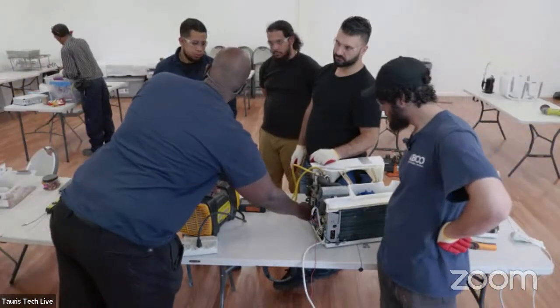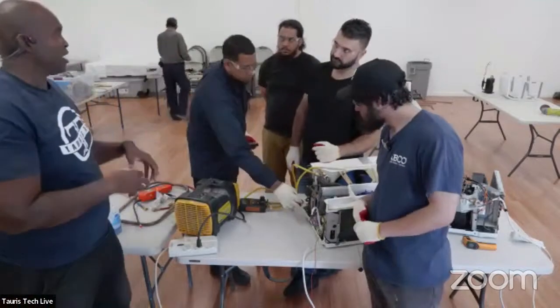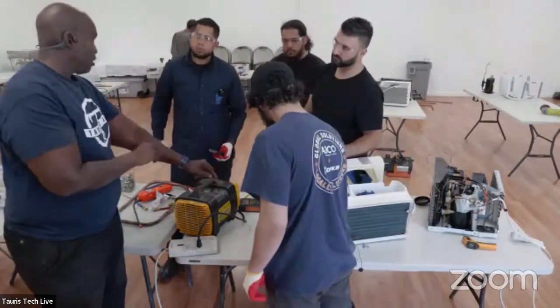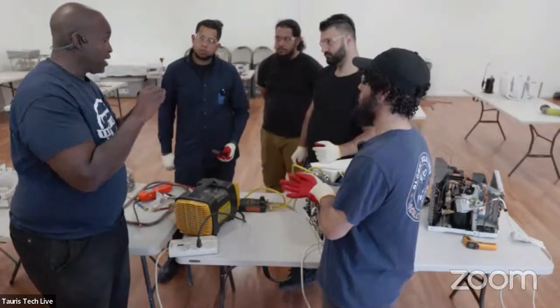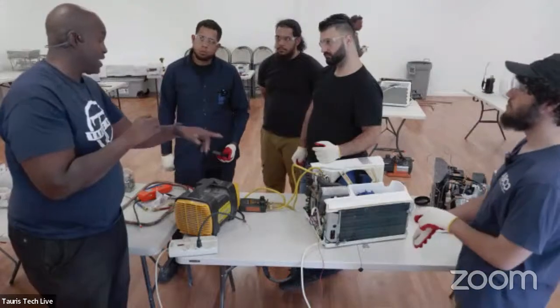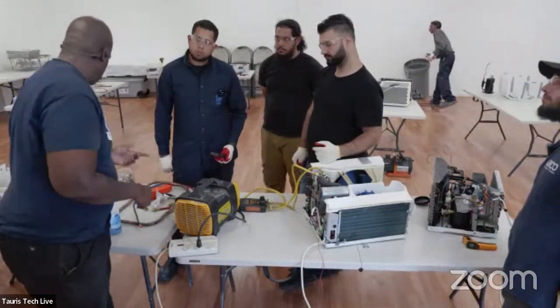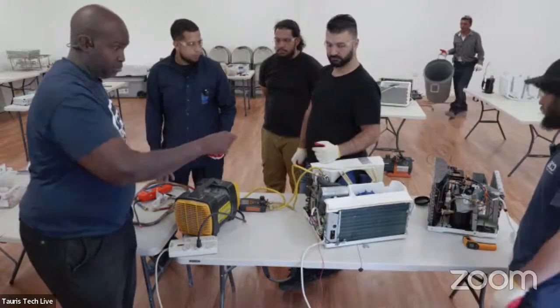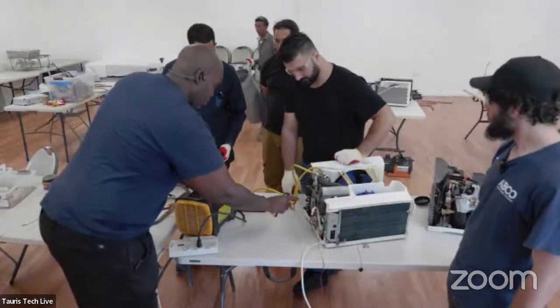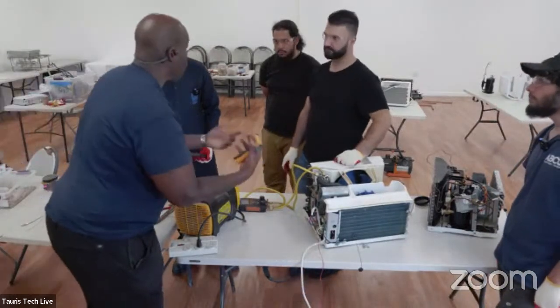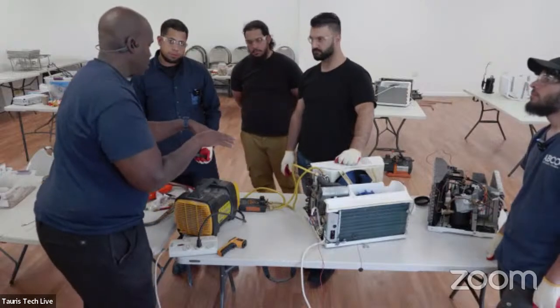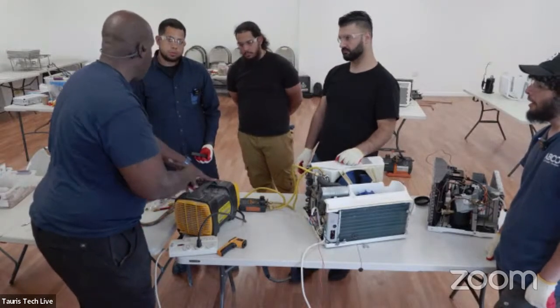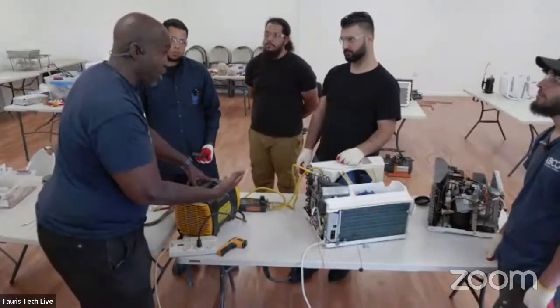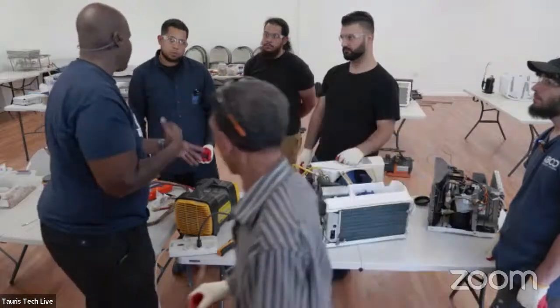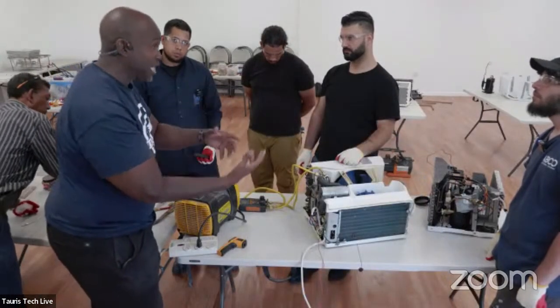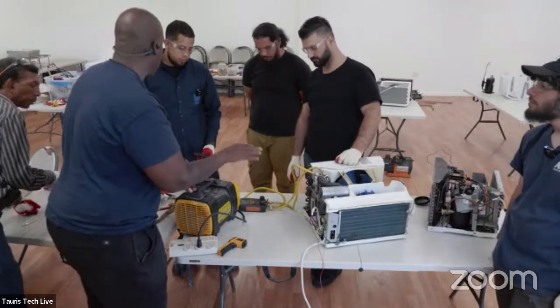It's slow because right now I'm boiling the refrigerant. As the pressure drops, it's boiling the refrigerant inside the oil. Any liquid in there is boiling — that's why the temperature is like that. I'm boiling it, that's why you run your recovery machine as long as possible, to boil the refrigerant out of the oil. It's the same reason when I'm evacuating with my vacuum pump — I'm trying to boil the moisture out. But right now, I'm trying to boil the refrigerant out.